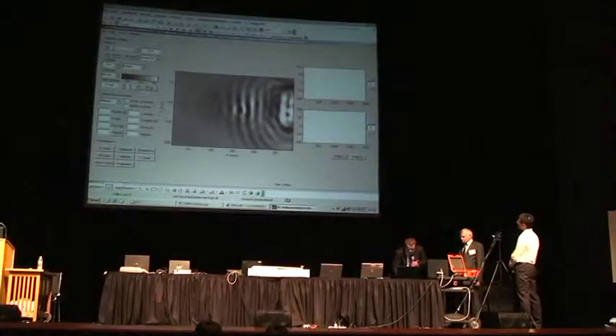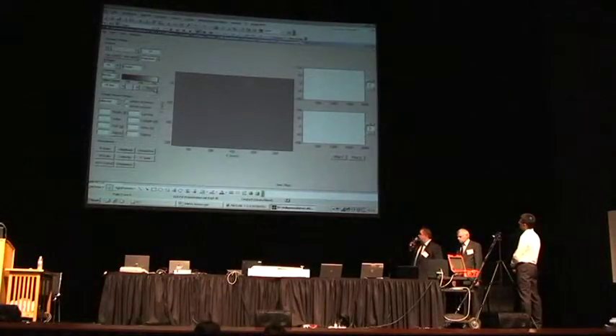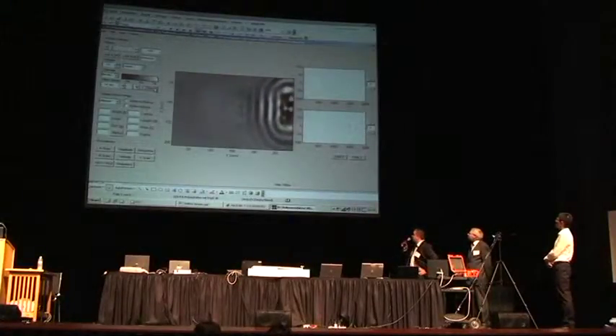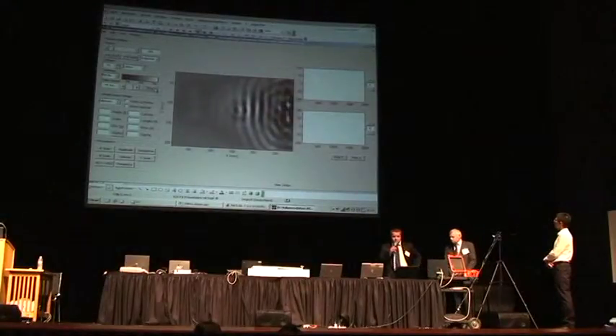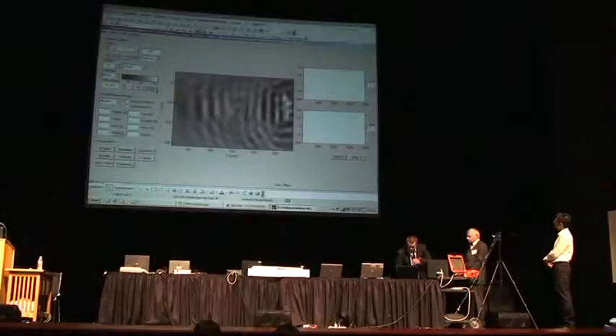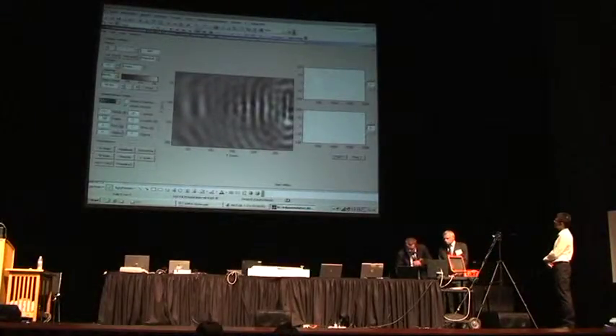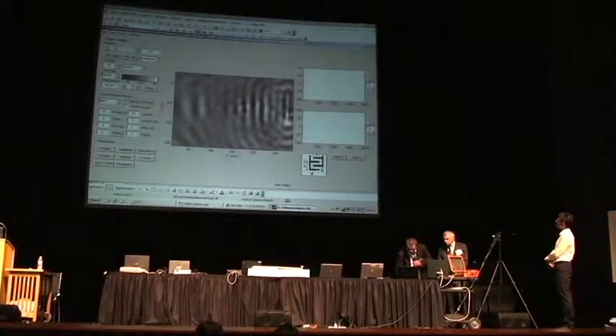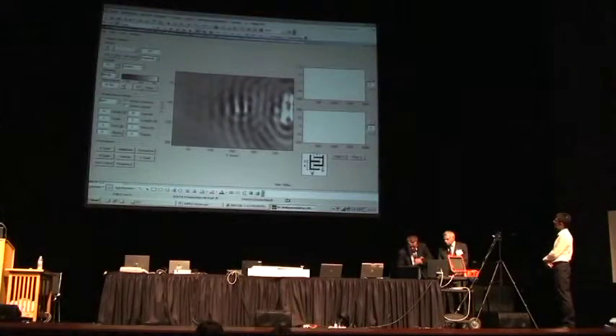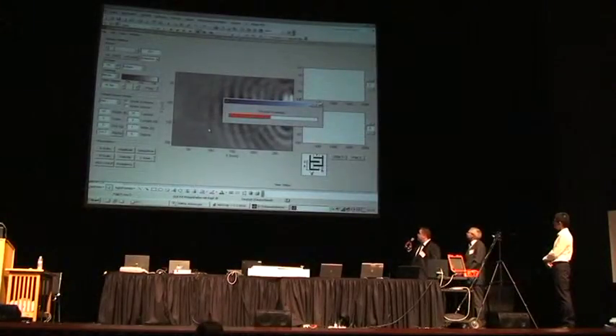We have here the pre-prepared data file in our analysis software. You see a video animation of the wave propagation and the interaction of the waves with the defect in the middle of the scan area. You see a mode conversion in this impact that causes wave propagation out of the center of the impact itself. Now we can use a virtual sensor, which we can define with this software and adjust it to the wavelength of the propagated wave out of this impact. Our software calculates the expected signal of this virtual sensor.